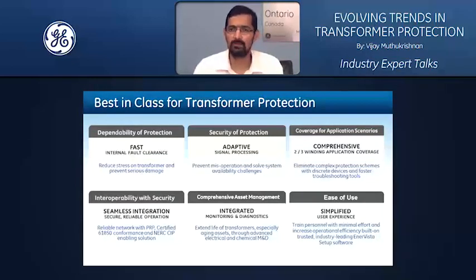Now, this is meeting your application need. You can just leave this much in a transformer protection relay and it will sit there and protect your transformer. But you want that device to be connected to the rest of your network, with the ability to build interlocks and control the breakers using the same relay. That is where you need interoperability as a next stage. Here comes a variety of networking architectures. It can be a simple Ethernet or a dual Ethernet, advanced PRP for reliable networking communications, or a very basic serial communication. You can have any type of network in your system. On top of that, you add a variety of protocols like Modbus, DNP, 61850, and so on.